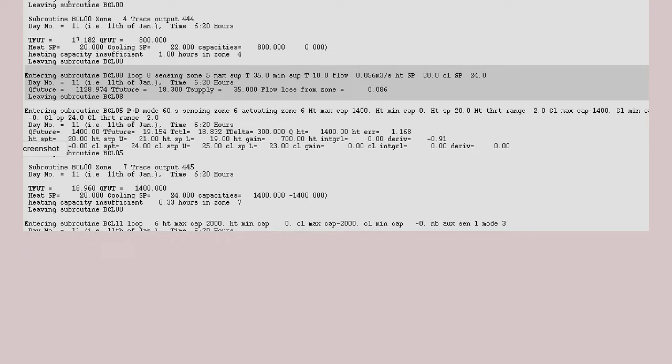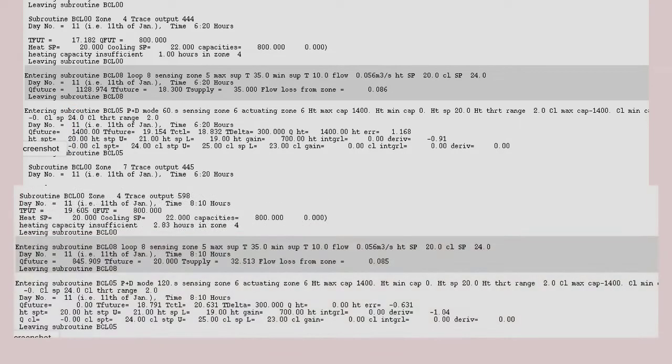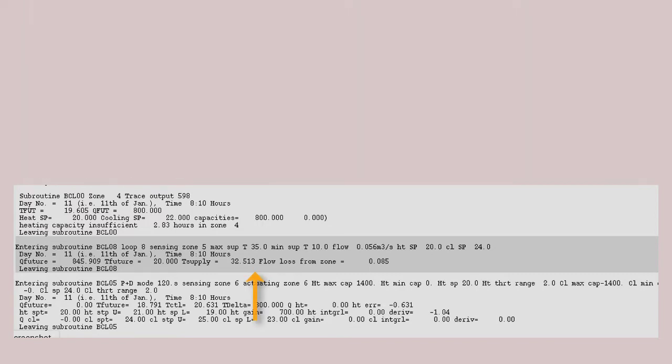Here's a short portion of such a trace file a few moments after the heating setpoint has been reset from 15 degrees to 20 degrees. So it's having to run at its maximum heating temperature. And the heat carried by that warmed air is less than the capacity that we might be wanting to use in other rooms. So we might expect a slow response. And some hours later, the trace indicates a lower supply temperature.